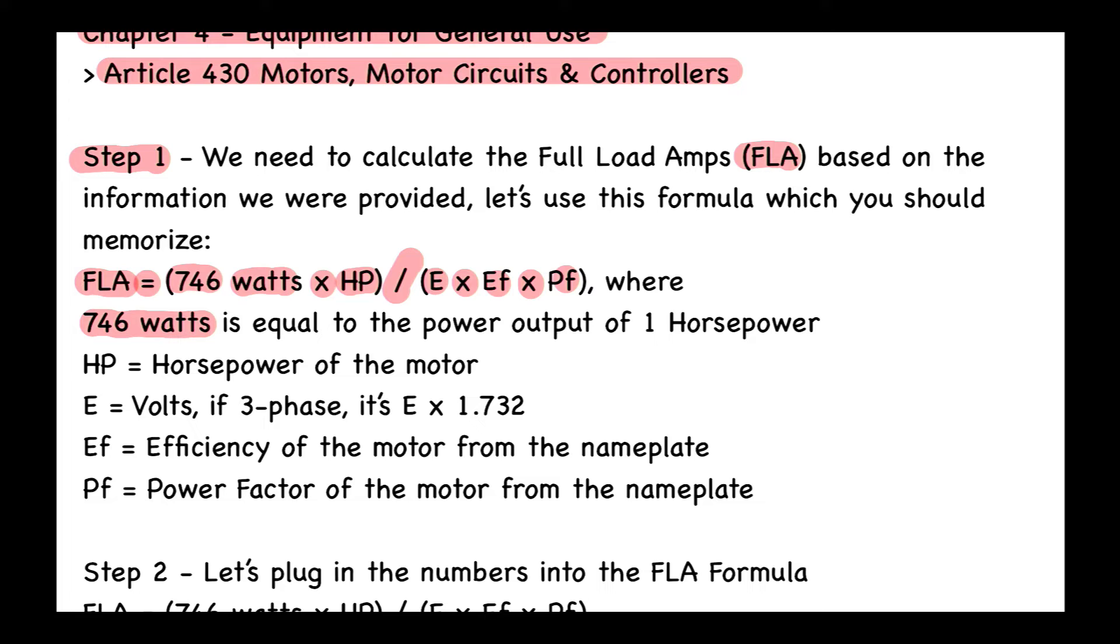HP stands for the horsepower of the motor. E is for volts. If it's three-phase, then we have to take E times 1.732, and again that's for three-phase. EF is equal to the efficiency of the motor from the nameplate. PF is equal to the power factor of the motor from the nameplate.